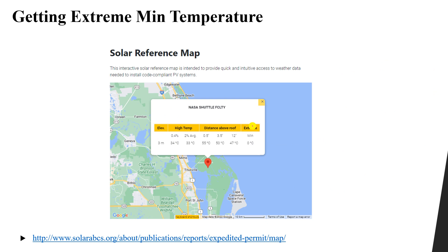In this lesson we discussed the maximum voltage of a PV system and why it is important in our design. When designing a PV panel system, we must ensure that the modules connected in series do not exceed the maximum system voltage at extreme minimum temperature conditions.